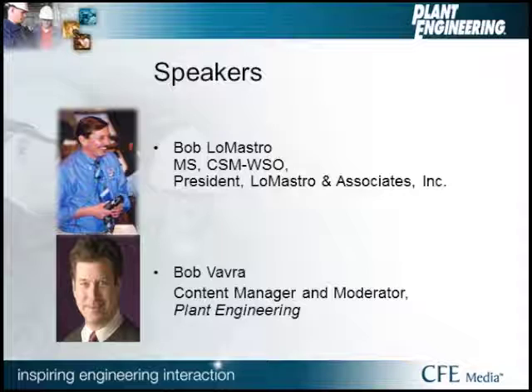Another question in from our readers, are meters and instrumentation permanently installed in power distribution equipment acceptable for verifying power has been disconnected, or does an electrician in PPE still have to open the covers and take manual voltage readings? Well, the thing we have to accept is that because that meter is showing 0 doesn't mean that the meter isn't damaged. It's a great feature so that we don't have to regularly go in and test.